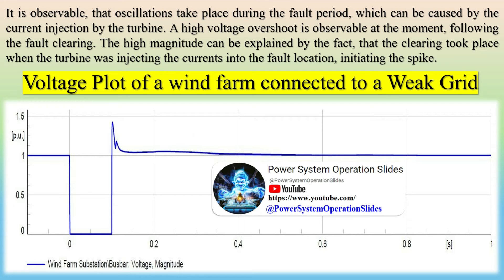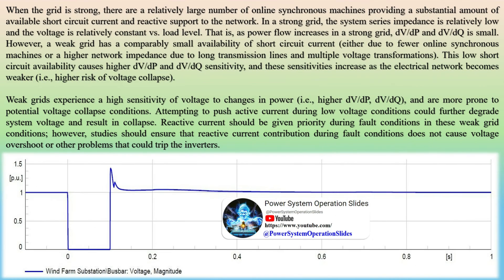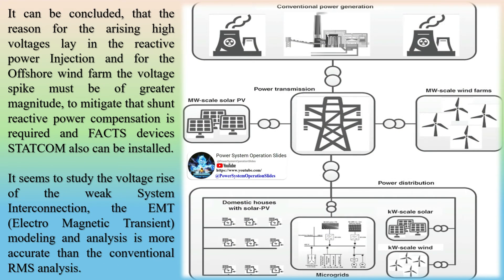When the grid is strong, there are a relatively large number of online synchronous machines providing substantial short-circuit current and reactive support to the network. In a strong grid, the system's series impedance is relatively low and voltage is relatively constant versus load level — meaning DV/DP and DV/DQ are small as power flow increases. However, a weak grid has comparably small availability of short-circuit current due to fewer online synchronous machines or higher network impedance from long transmission lines and multiple voltage transformations. This low short-circuit availability causes higher DV/DP and DV/DQ sensitivity, and these sensitivities increase as the electrical network becomes weaker, raising the risk of voltage collapse.